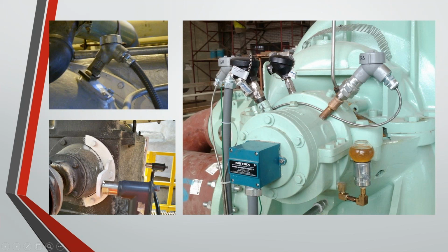And we may even see an increase in vibration as a result if we're exciting the natural frequency of that cantilever beam. So is this sensor actually measuring the vibration in this housing? I'd say we have no idea. We don't know what this thing's measuring. Could be measuring close, could be far away, but we want to avoid cantilever beam style mounting. So that's a big no right there.